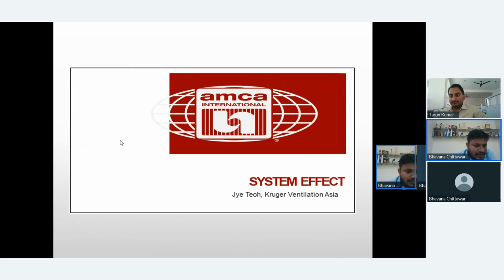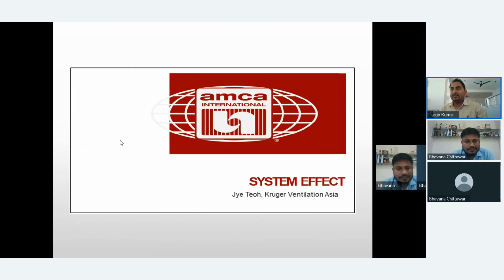Another question is: sir, what is the EC fan and EC plus fan? How are they consuming less power compared to DIDW fans with induction motors? See, the EC fan is a very good concept that came into the market for the energy saving point of view. Basically, the EC and EC plus fan is a complete BLDC motor fan, and it is not necessarily that it saves much more power than the DIDW fan. It again depends upon your CFM and static pressure.